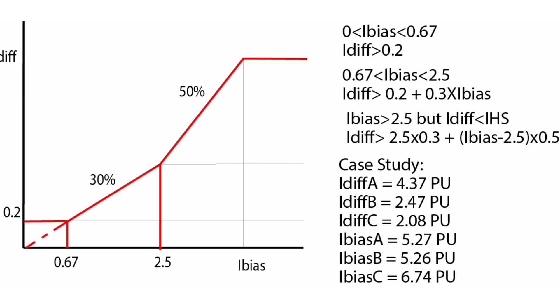If the differential current is less than that threshold, the relay will remain in the blocking or restraining region. The third region applies when the bias current is greater than 2.5 per unit but the differential current is less than the differential high-set value. For this region, the differential current must be greater than 0.75 plus (I_bias minus 2.5) times 0.5 to remain in the tripping region.